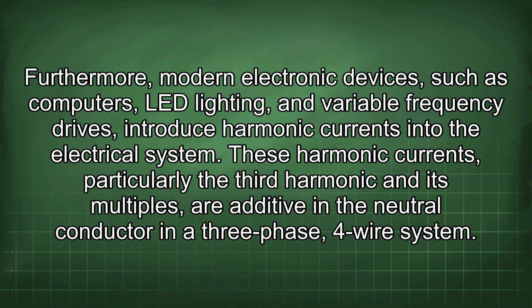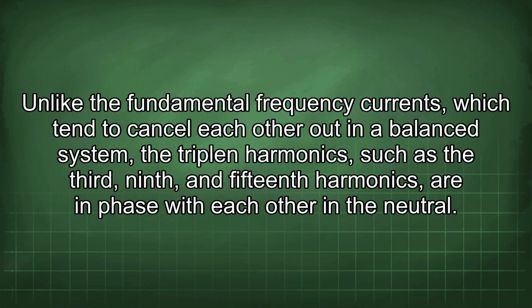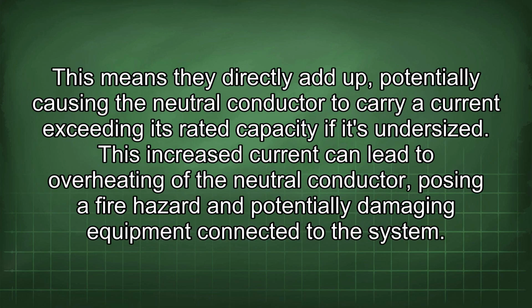Furthermore, modern electronic devices, such as computers, LED lighting, and variable frequency drives, introduce harmonic currents into the electrical system. These harmonic currents, particularly the third harmonic and its multiples, are additive in the neutral conductor in a three-phase, four-wire system. Unlike the fundamental frequency currents, which tend to cancel each other out in a balanced system, the triplen harmonics, such as the third, ninth, and 15th harmonics, are in phase with each other in the neutral. This means they directly add up, potentially causing the neutral conductor to carry a current exceeding its rated capacity if it's undersized. This increased current can lead to overheating of the neutral conductor, posing a fire hazard and potentially damaging equipment connected to the system.